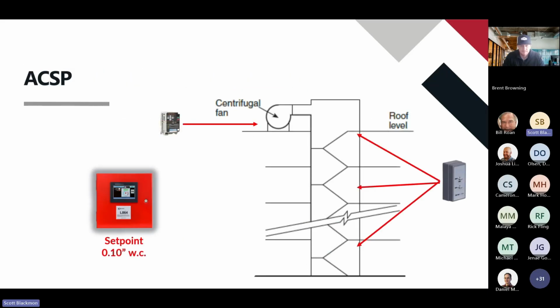When we take a look at how this system is installed, it's very simple. Basically, we've got a VFD at the fan. We have pressure sensors high, medium, and low in the stairwell. And then we're going to have our 864 mounted somewhere near the FSCS, usually in the fireman's closet, somewhere where all the control systems are, so that the fireman is able to see the system, react to it, shut it off, change it, whatever needs to happen, however the firemen want to override it.